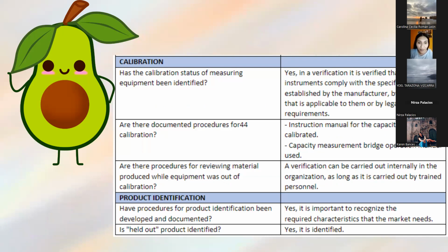In the calibration, has the calibration status of measuring equipment been identified? In the result, yes. In a verification, it's verified that measuring instruments comply with the specification established by the manufacturer, by a standard that applies to them, or by legal requirements. Are there documented procedures for calibration, instruction manuals for the capacity to calibrate, and operation manuals used? Is there a procedure for reviewing material produced while equipment was out of calibration? A verification can be carried out internally in the organization as long as it's carried out by trained personnel.